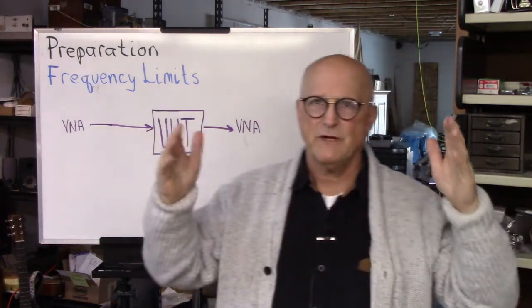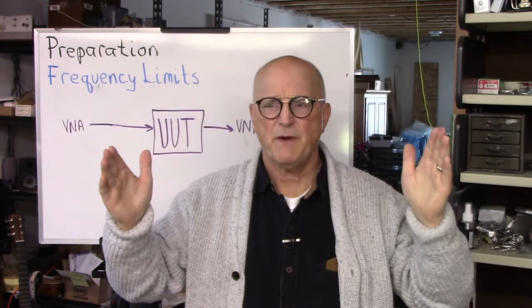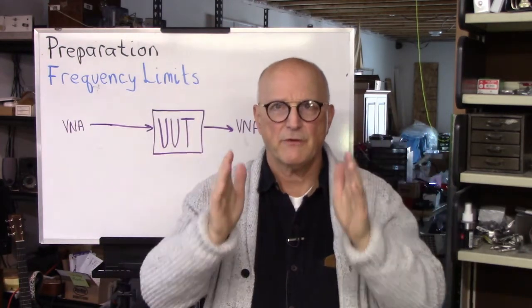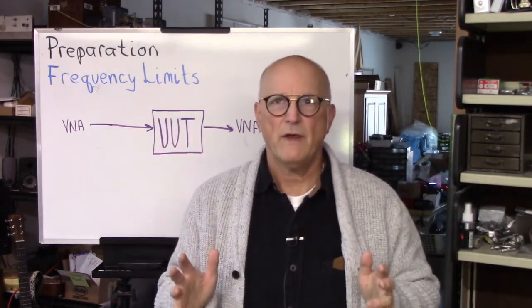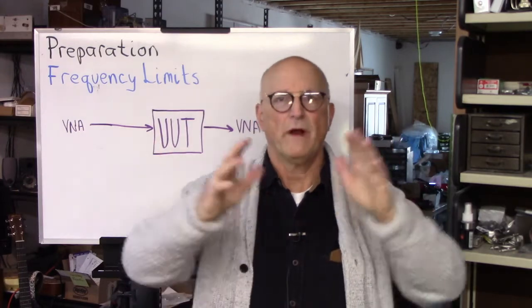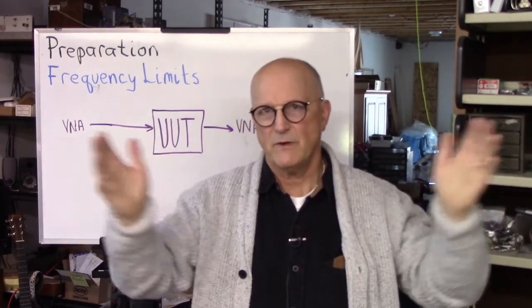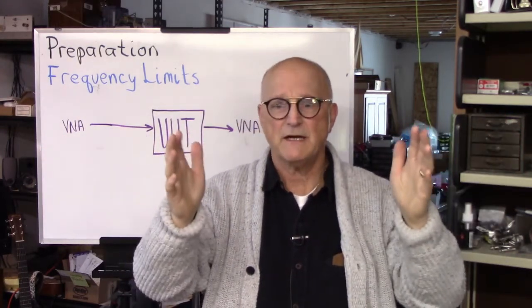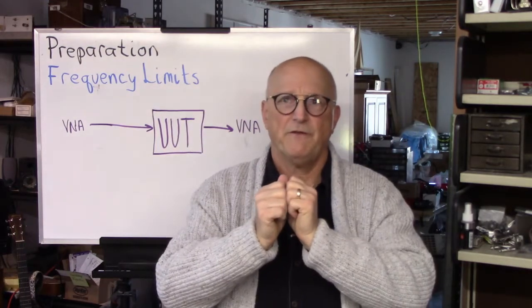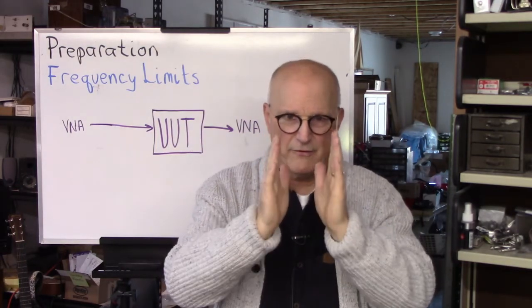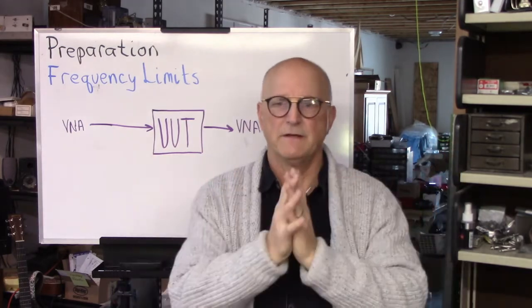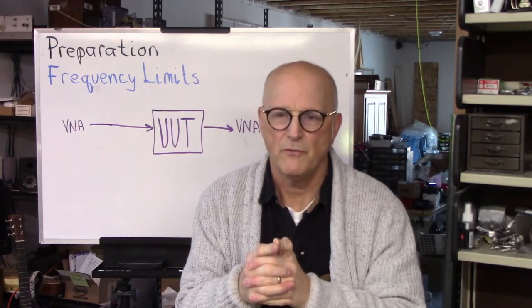Now, if you calibrate to a wider frequency span and then measure to a narrower one, that's okay. You don't want it too much wider. You want to try to keep it as close as possible. But you definitely don't want to calibrate to a narrow one and then measure wider. That's kind of a big no-no.